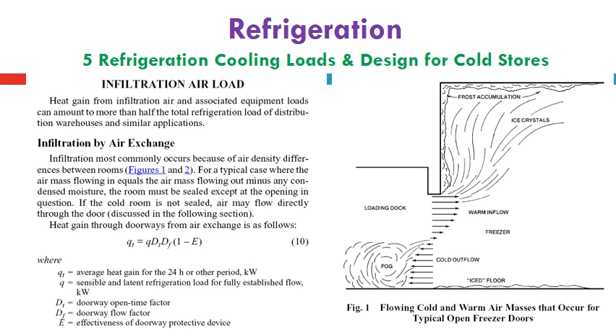So it's recommended to use an air interlock area between the refrigerated space and the outside, the loading dock, which may include hotter air than the colder air inside the refrigerated space, especially for freezing. And we can see the fog in the lower part due to the cold outflow air at the door opening, so it can generate a fog of air or moist content due to this heavier air compared with the air outside.